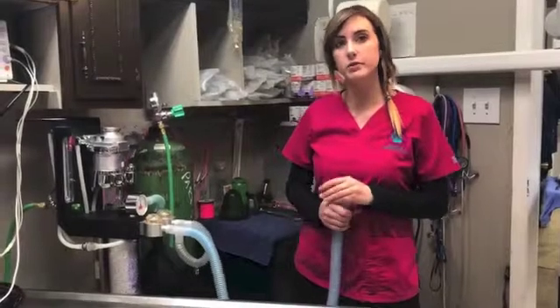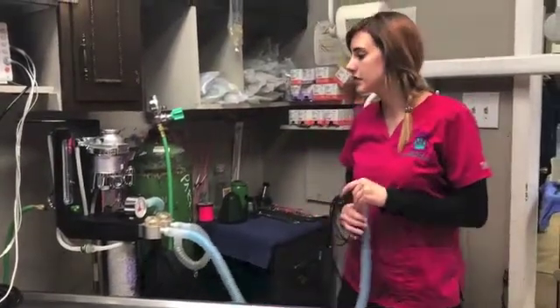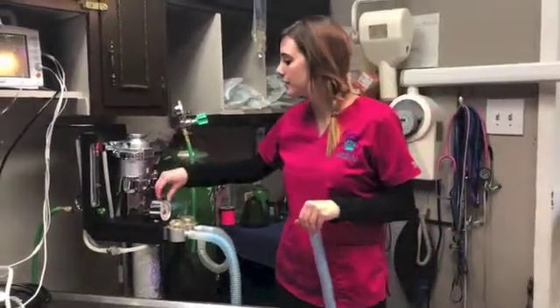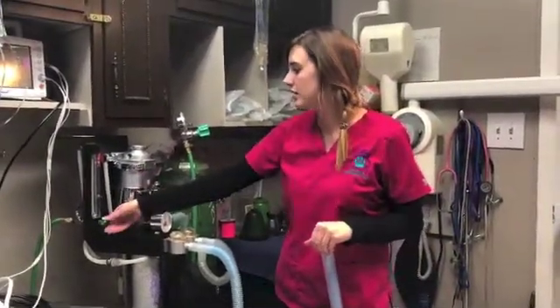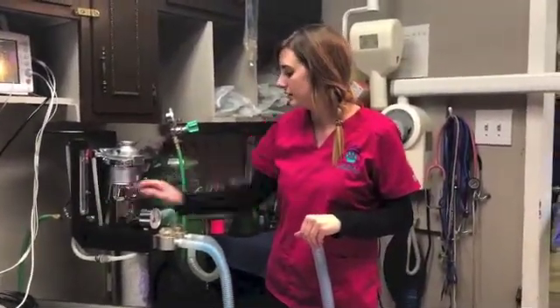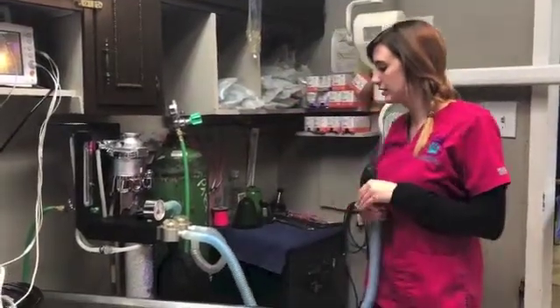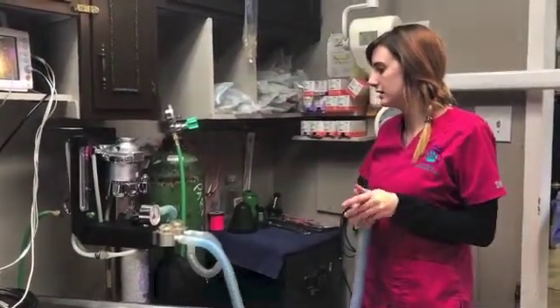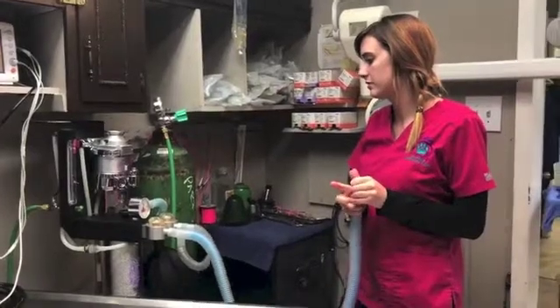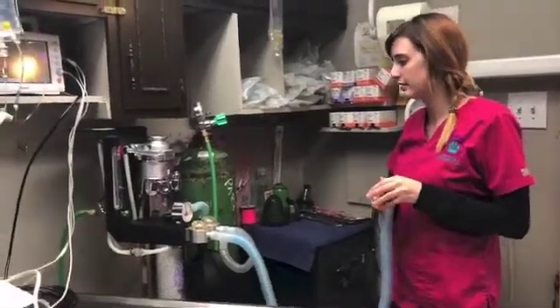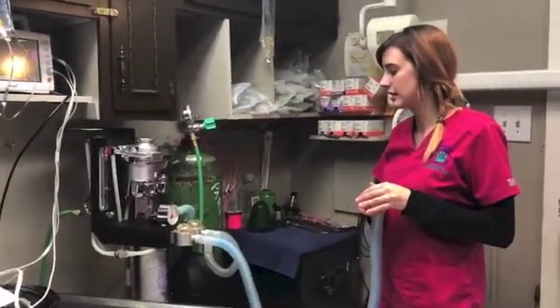And I'm done with that. I'm going to perform a leak test on our anesthetic machine. The pop-off valve, I'm going to turn it closed. I'm going to turn our oxygen all the way up. Fill this bag, and when it hits the 20, that's when I will let it sit and see if it leaks.